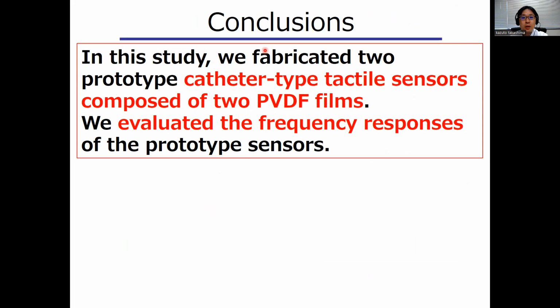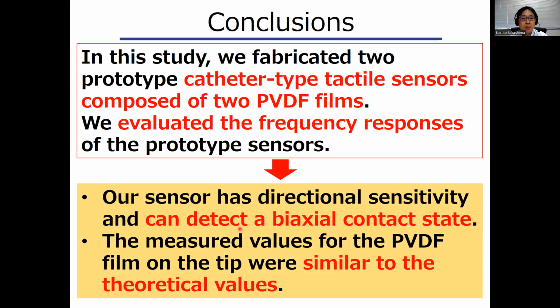In conclusion, in this study, we fabricated two prototype catheter-type tactile sensors composed of two PVDF films. We evaluated the frequency responses of the prototype sensors. Our sensor has directional sensitivity and can detect a biaxial contact state. The measured values for the PVDF film on the tip were similar to the theoretical values.